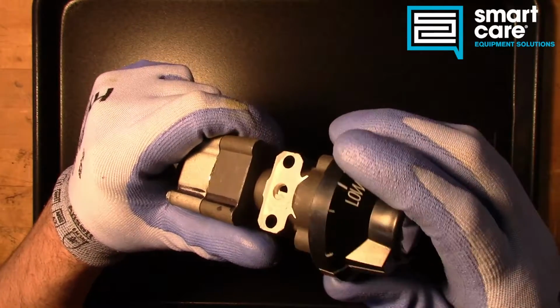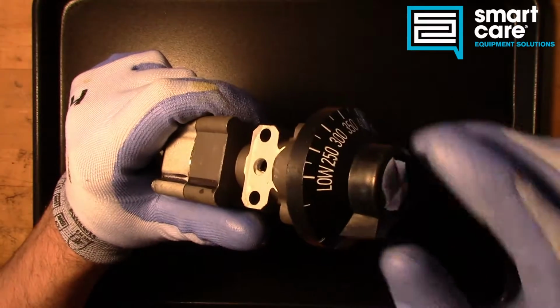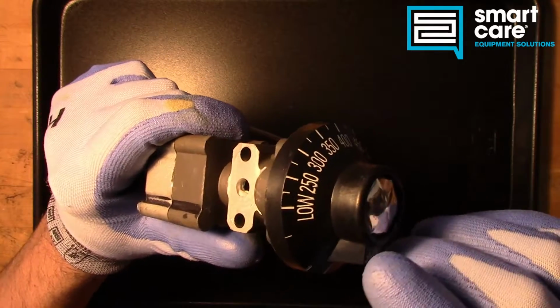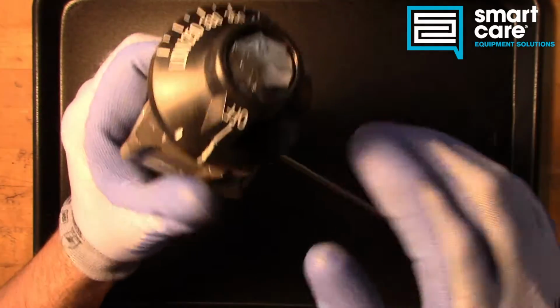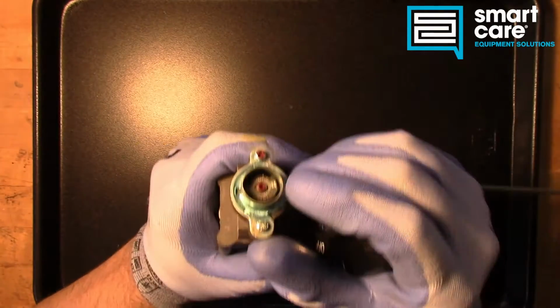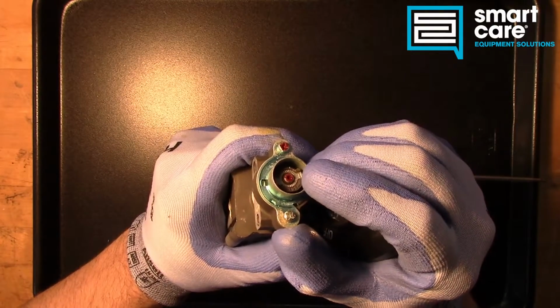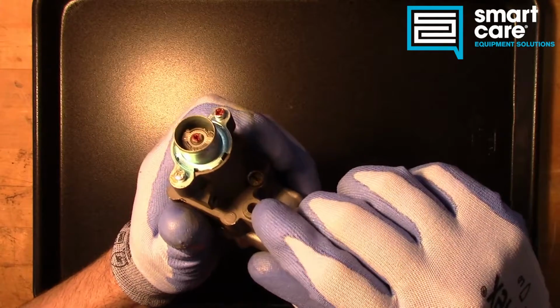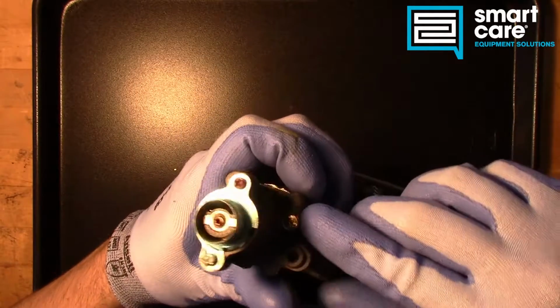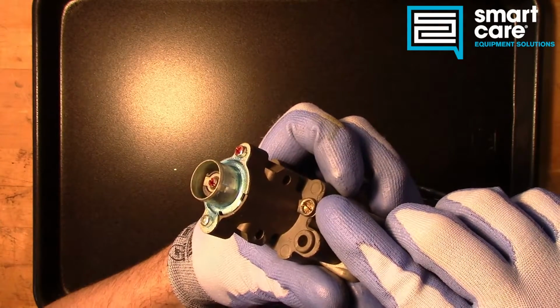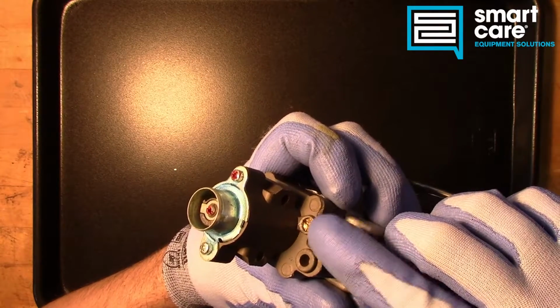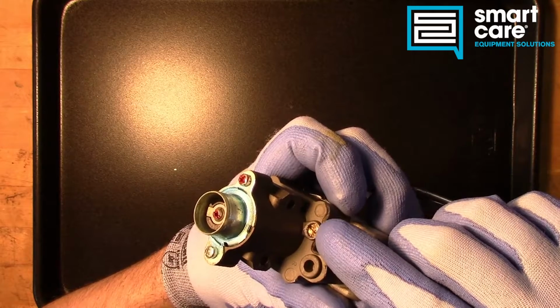These thermostats result in a lot of service calls when they're newly installed, and that's for one of two reasons. The first one is the calibration screw down here is not set correctly, and the second one is that the bypass is not set correctly. In this particular thermostat you can see the bypass screw here has been cranked shut, and it's actually been cranked shut with enough force that the screw itself is damaged.